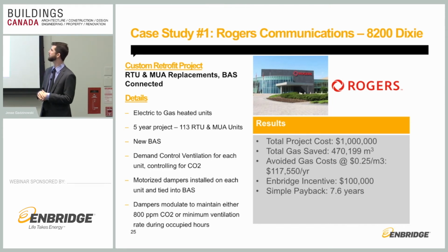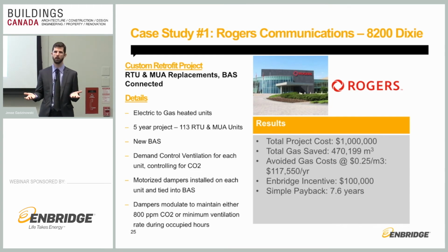So significant savings there, a large project. They put motorized dampers on the new units so that they could control for the carbon dioxide, and then tie that into the BAS. So you could see what you were going to do. It was all there on the BAS output screens. And for this, the project was $1 million.